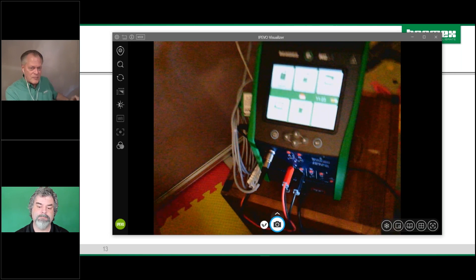I forget the exact number, but it has a little transition here, and we're able to put the Callendar Van Dusen coefficients for this probe into the calibrator, which is how we achieve good accuracy with this reference probe. This is a standard 385, 100 ohm platinum 3-wire transmitter. If I scroll down here, you can see the terminals on the front of the calibrator. This is my reference probe - it has a LEMO connection and is actually a 4-wire connection, and as I said, it's getting corrected with a coefficient.